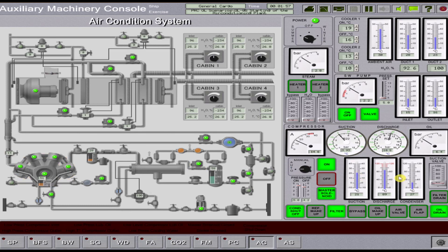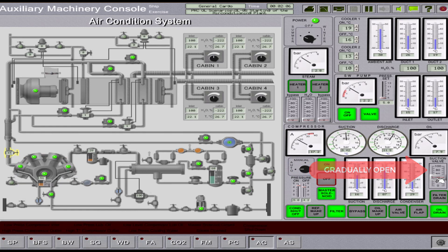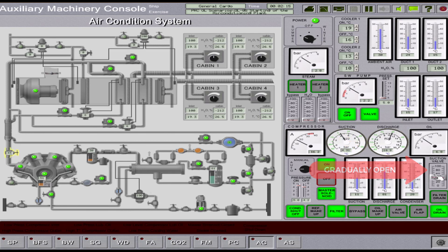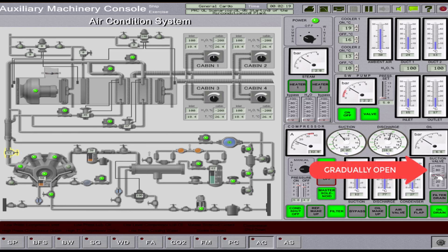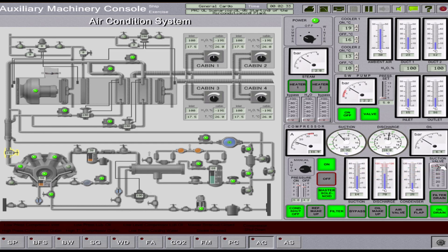Then, gradually open the suction valve. Once you open gradually the suction valve, always monitor the suction pressure gauge. If the suction pressure is going down, you open again your suction valve until you reach the 100% open. Then, you verify that the compressor is already running automatically.